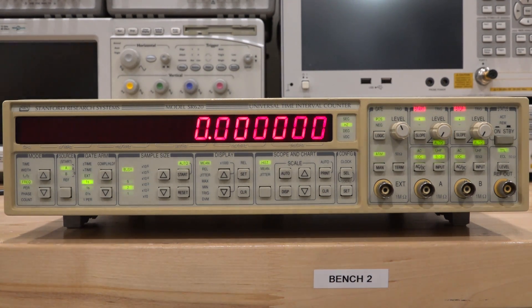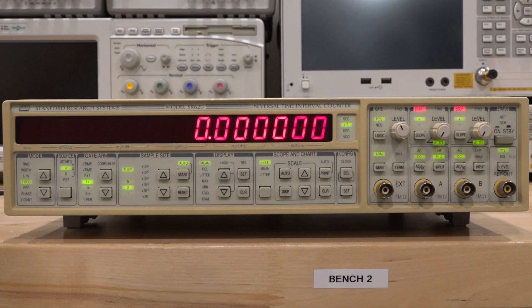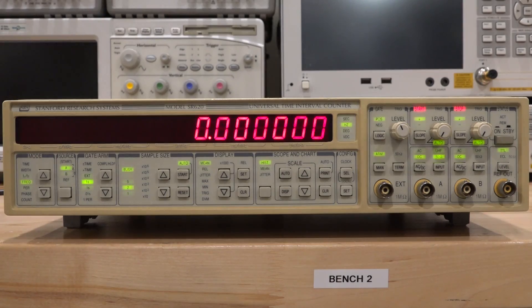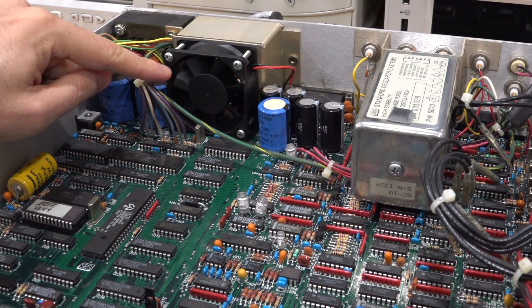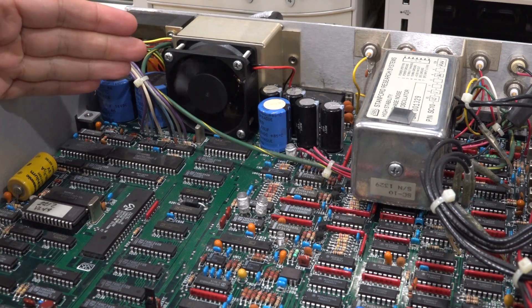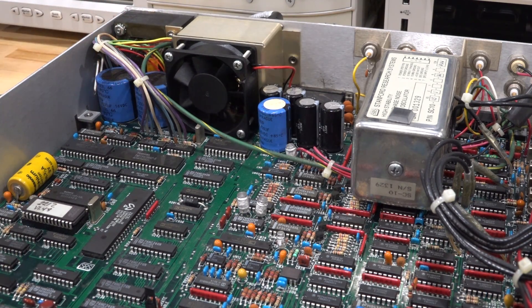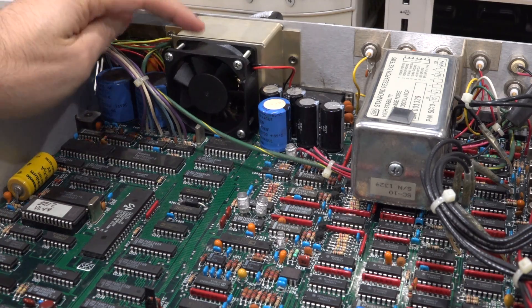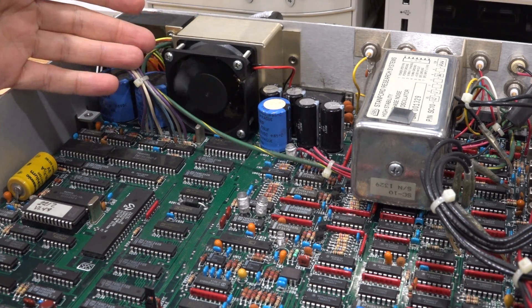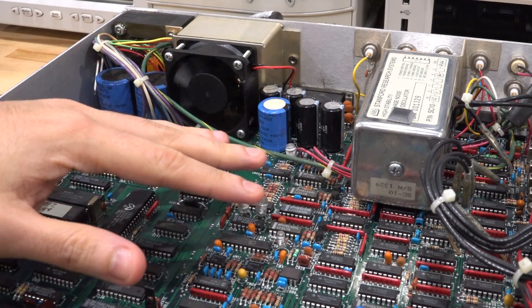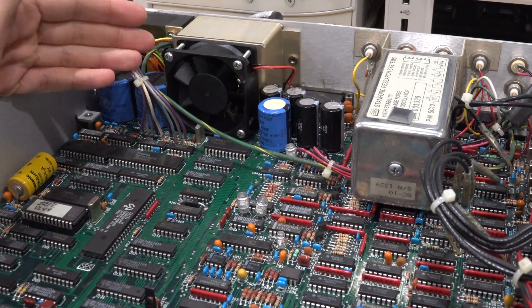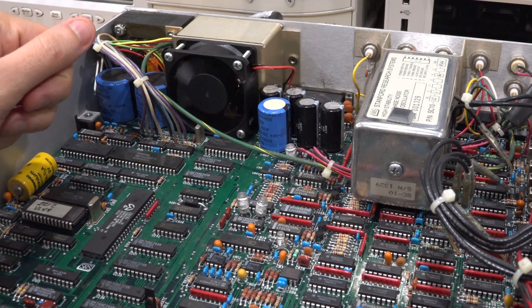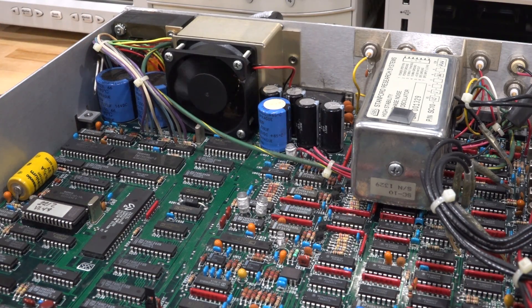So I was just about to go ahead and try and test it, do some experiments with it, and I noticed that there's something really annoying about the way the thermal design of this instrument actually works and about the way the fan works. Let me show you. There you go, so you kind of see that the fan pulsing here. There you go, it just turned off a little bit. Now it's going to run like this and then it's going to all of a sudden turn on full blast and then turn off. The reason for that is that there is a thermistor right behind the fan, and essentially the idea of the thermistor is that the air inside the instrument goes through the fan and it tells the fan how fast it should spin because that's the temperature inside of this instrument it is trying to regulate.